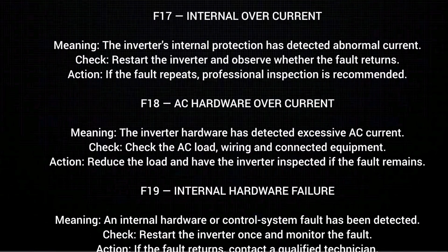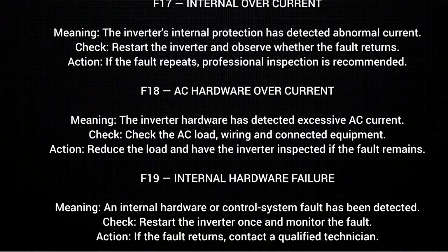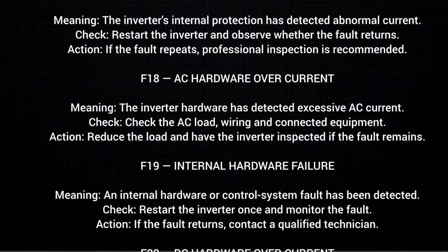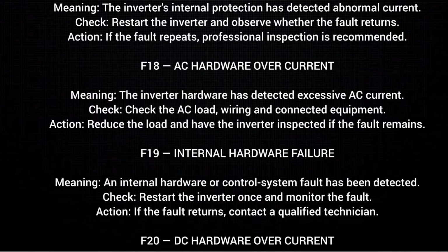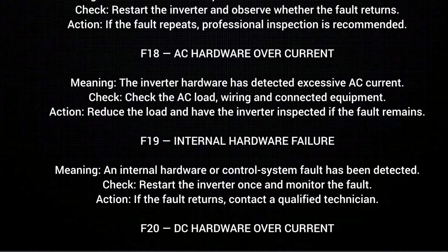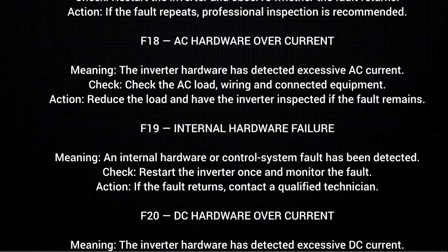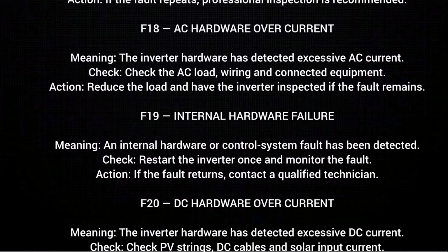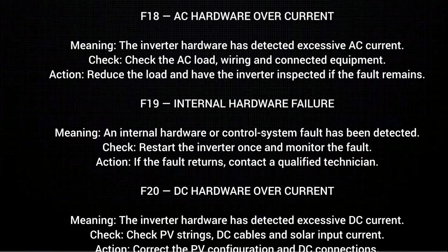F18 AC hardware overcurrent, meaning the inverter hardware has detected excessive AC current. Check. Check the AC load, wiring and connected equipment. Action. Reduce the load and have the inverter inspected if the fault remains.